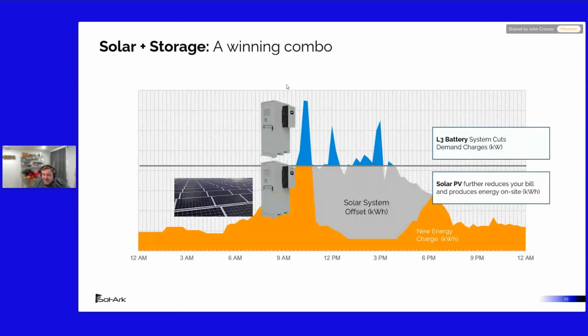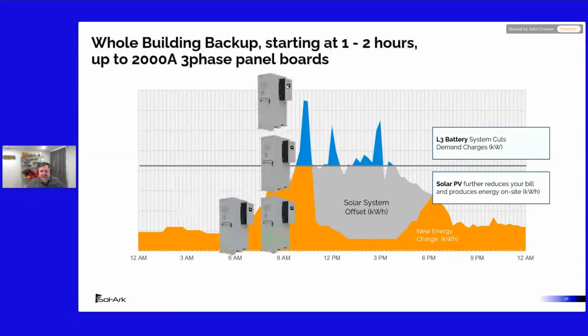By the time you get to two inverters and two battery cabinets, you might as well look at the entire load profile and consider whole building backup. Generally, by the time you're demand managing peak use—let's call that a third of the building—by the time you get to offsetting all of the building's demand, that's equivalent to saying the same system could back up the whole building for an hour or two. So why not just take a whole building backup approach at that point?